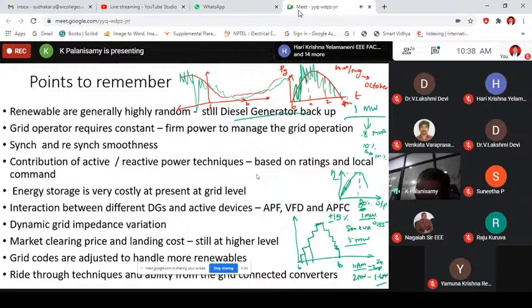By following the frequency of the grid, I can increase or decrease the active power injection, right? Of course, I need to have proper energy storage, or I need to have a proper mechanism, so that only then can I have the frequency regulation support. Okay. What about the reactive power? See, unlike voltage, frequency is constant throughout the grid. Whether you are measuring here or at Andhra Pradesh or Maharashtra, the frequency is constant if the grid is interconnected, right?